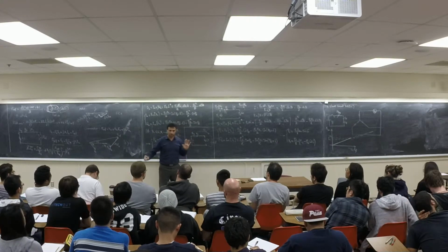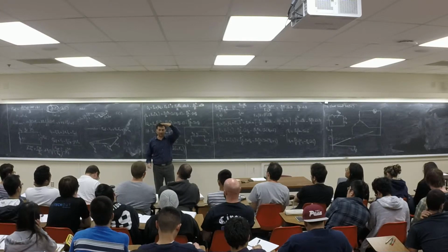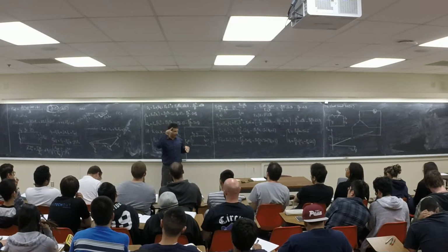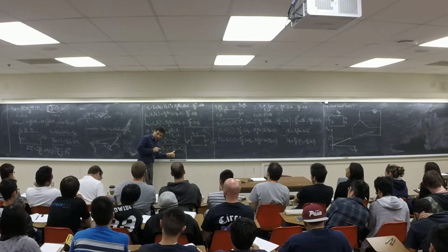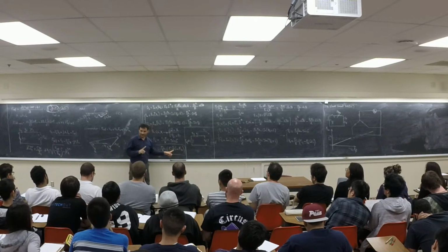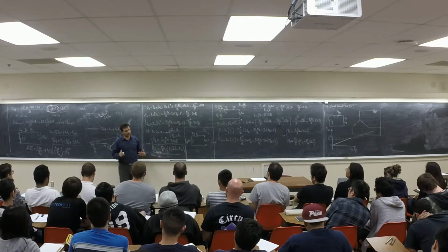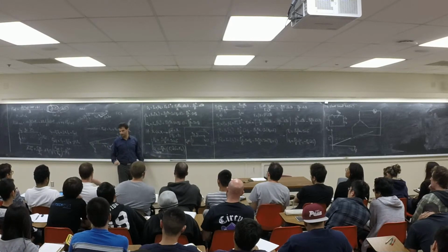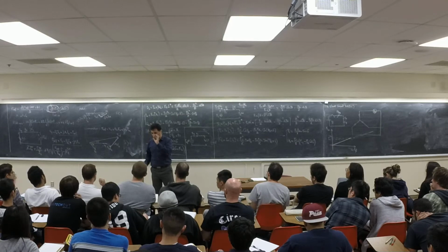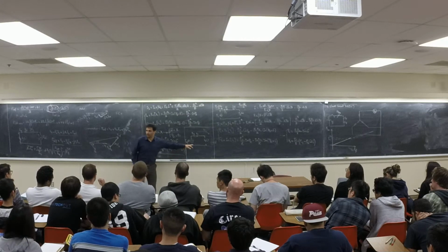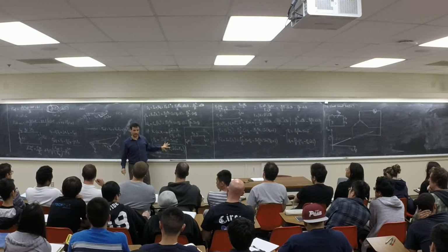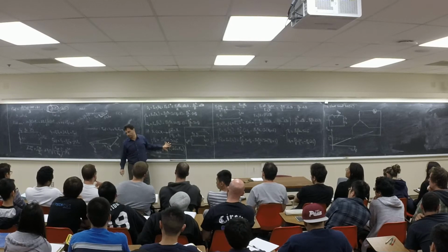Those are very nice for power factor correction. If you remember, with a capacitor the power factor changes in steps. I can jump from 0.9 to 0.92 to 0.94 to 0.96. The jumps are discrete. But here, with delta, it's continuous. I can change my delta 0.1 degree, 0.2 degree, 0.3 degree. This is the advantage. If somebody tells me I need a 0.9352 power factor, with a capacitor I would need a very, very small capacitor to do that. But here, I can set my angle to give you that power factor. If the synchronous machine is only used for power factor correction, they call it a condenser, if you hear about it.